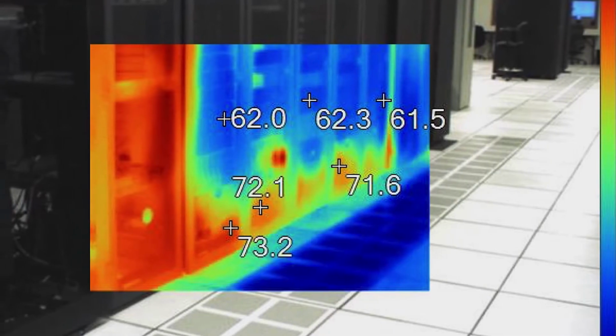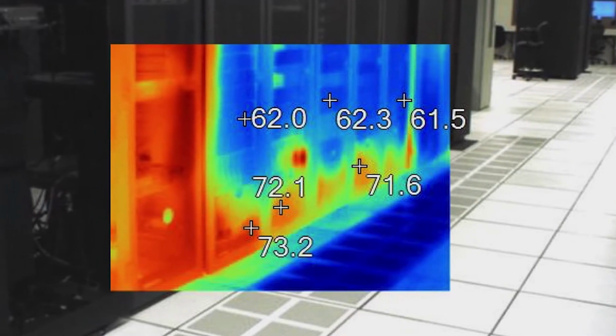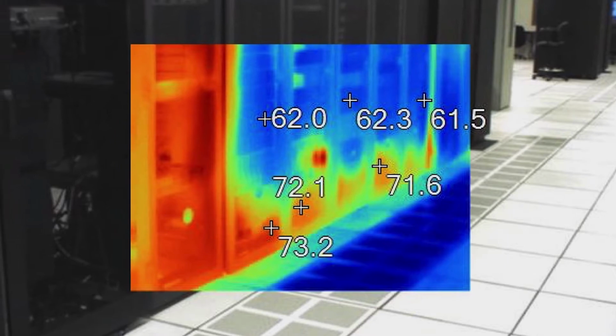When this space is sealed, it prevents cold air from leaving the cold aisle. Often in a fully contained configuration, cold air will leave underneath the cabinets, or in a partial containment or no containment situation, hot air from the hot aisle can flow underneath the cabinets, elevating intake temperatures of the IT equipment.